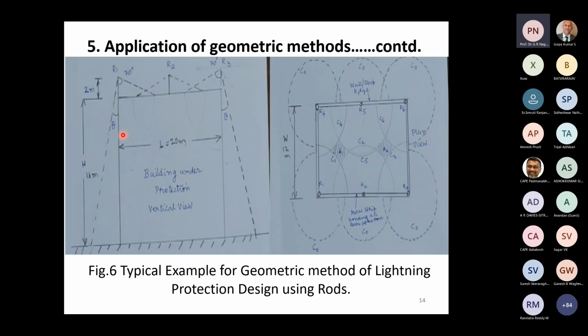Corresponding to that 18 meters, you will find that the protective angle is approximately 20 degrees. So you will see that the cone of semi-conical angle 20 degrees is to be used for finding out the area which is protected.